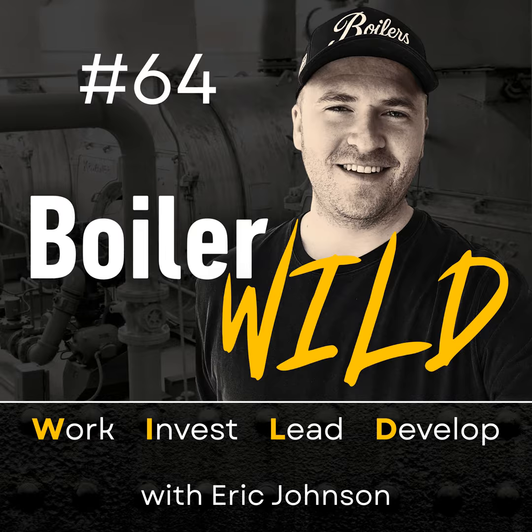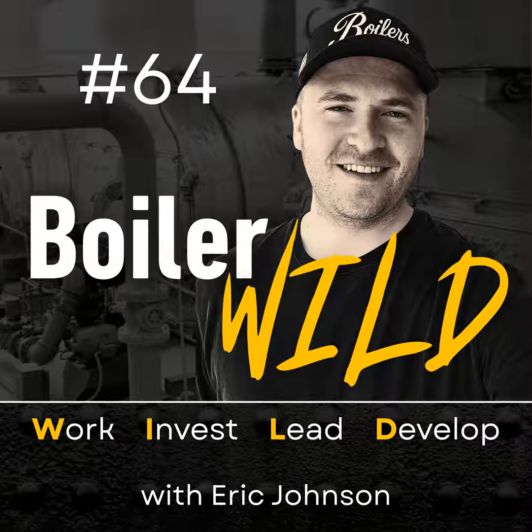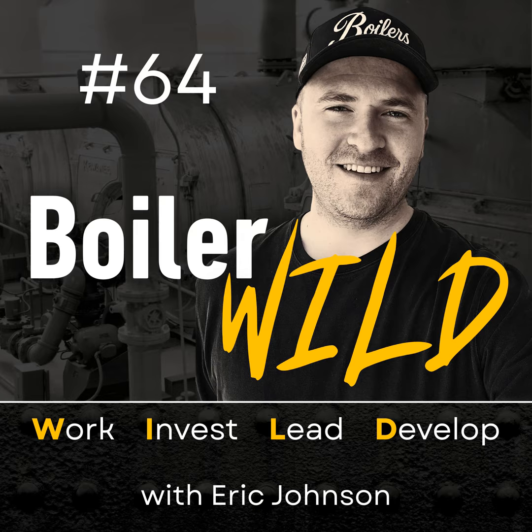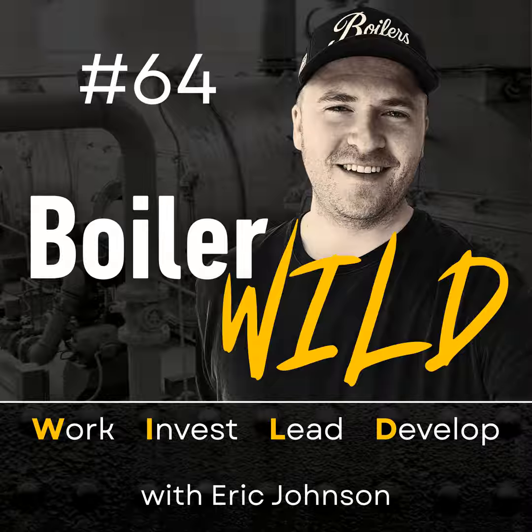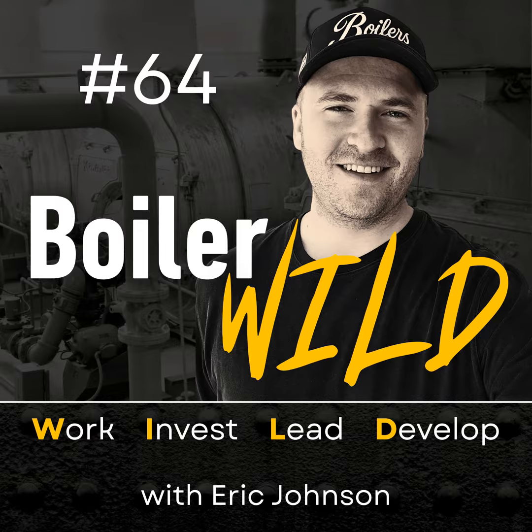A typical scenario where this is an issue as well for service technicians is you go out to a site for an annual inspection, the boiler gets opened, maybe there's some tubes that need to be replaced, and they hydro the boiler. By hydro the boiler, it means they filled the boiler up with water 100% of the way, and then most often you can just use the pressure of the feed water pumps to add pressure to the boiler to see if the repairs are leaking. So the new tubes are leaking, or if any other tubes are leaking. If that is not satisfactory for the situation, you need a pump that is going to be able to pump up the boiler to a certain pressure, and that is going to depend on the MAWP of the boiler. But anyways, you pump that up, and if you pump up the boiler to the MAWP, you will probably trip the high pressure limit on a steam boiler.